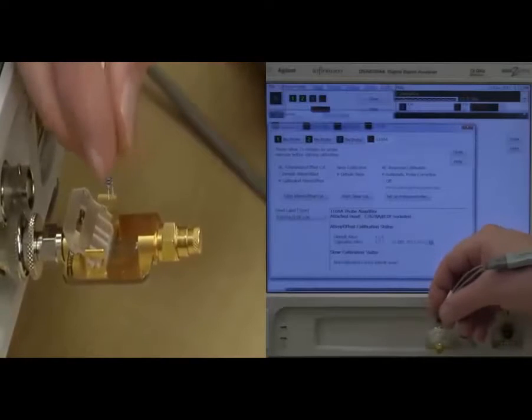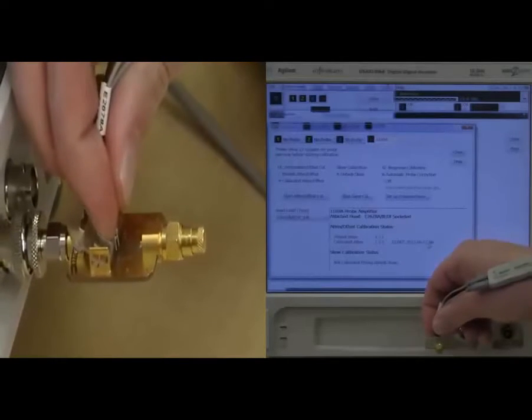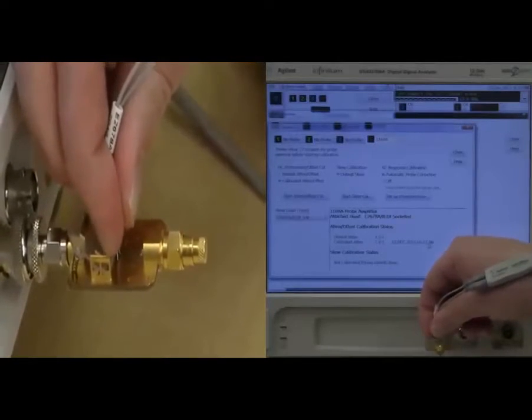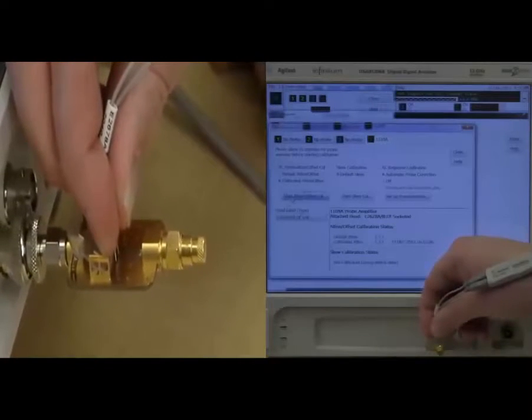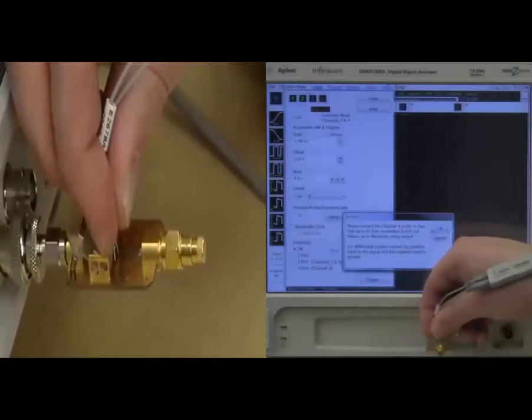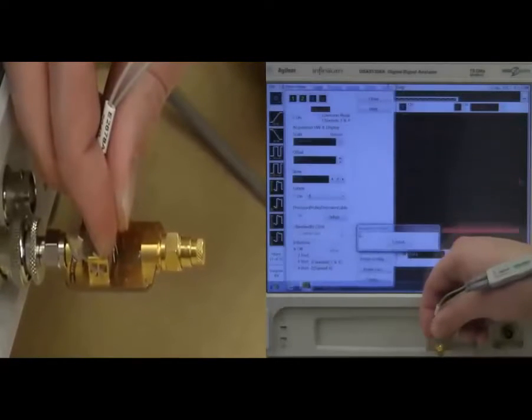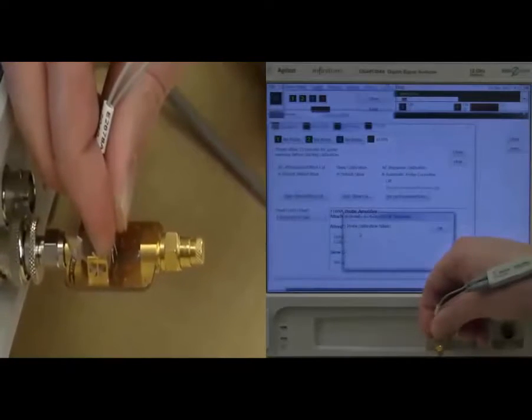Now, if you mess this up, if you mess up the polarity, you notice in the previous screen image that the signal went up the screen. If you mess up the polarity, what'll happen is that the signal will go down the screen, and that just means flip the polarity on the probe. We saw there it went down. The probe calibration failed.